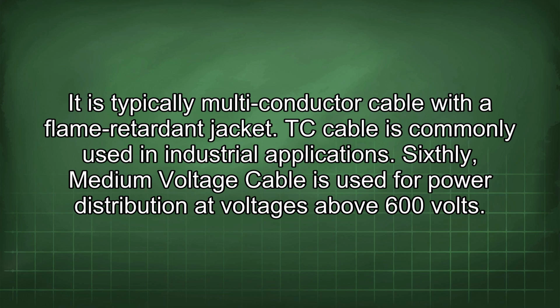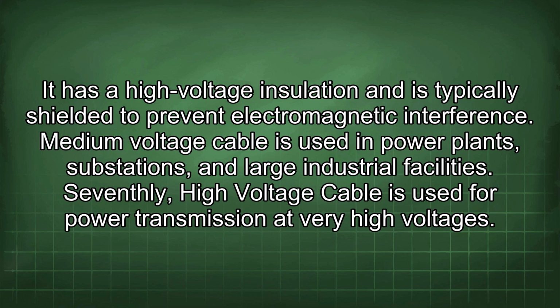Sixthly, medium voltage cable is used for power distribution at voltages above 600 volts. It has a high voltage insulation and is typically shielded to prevent electromagnetic interference. Medium voltage cable is used in power plants, substations, and large industrial facilities.